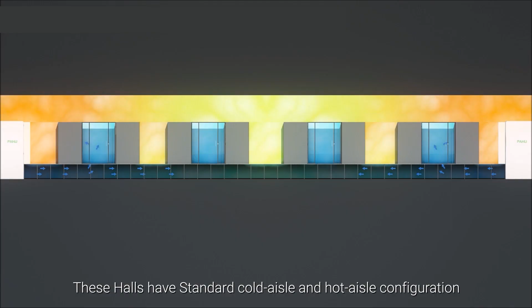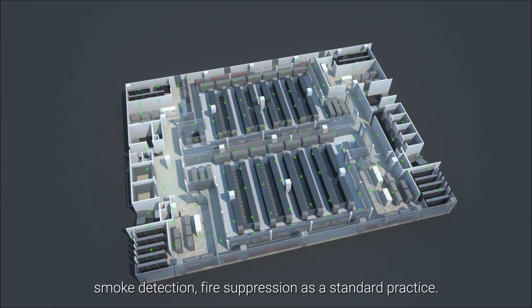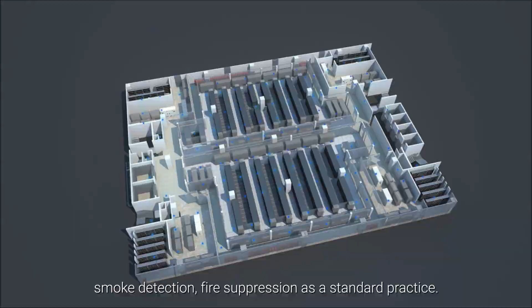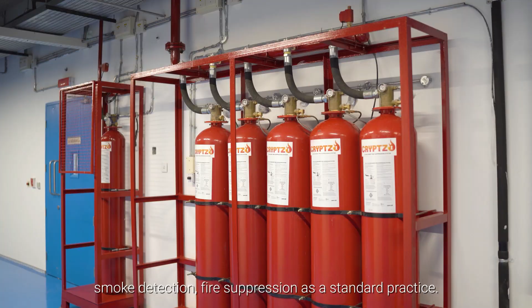Here are the data halls. These are classified into enterprise, medium density, and hyperscale high density halls, carrying 800 mm wide and 600 mm wide racks respectively, of standard style. These halls have a standard cold aisle and hot aisle configuration with raised floor and cold aisle containment implementation. Underfloor services include power cables, grounding, smoke detection, fire suppression. Overhead services include communication cables, smoke detection, fire suppression as a standard practice.